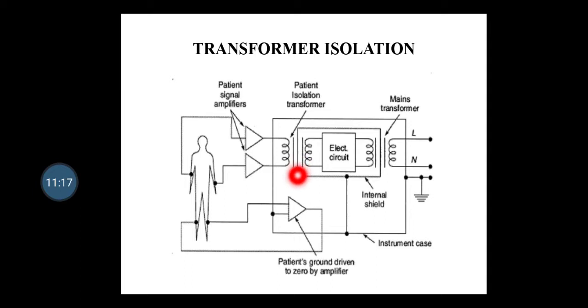This is the basic diagram of transformer isolation. Here we provide isolation through this transformer circuit. The patient signal will be amplified, and once we give the signal to the transformer barrier circuit, only then will the signal be received by the electric circuit and come to the main amplifier. Here also we have one barrier. Once the barrier is excited, only then is the signal received from the secondary to the primary. In that manner, we give electrical isolation between the patient input and the output circuit.